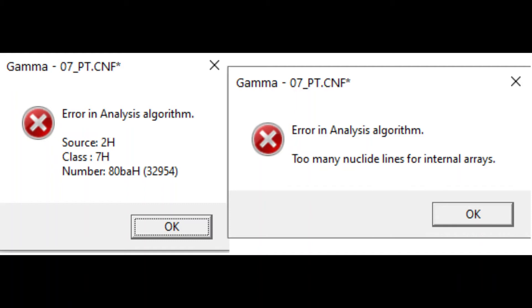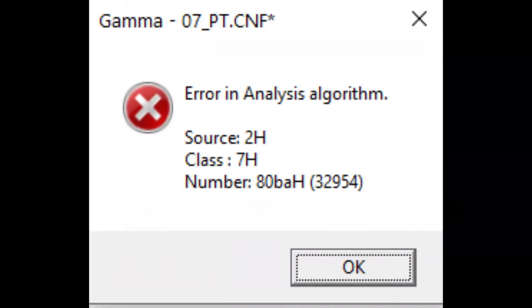Both have to do with finding too many matches in the spectrum. My guesses about these two error messages are that the 80baH error message indicates Genie will have to include too many gamma lines in its output report. Therefore, it fails in step four.